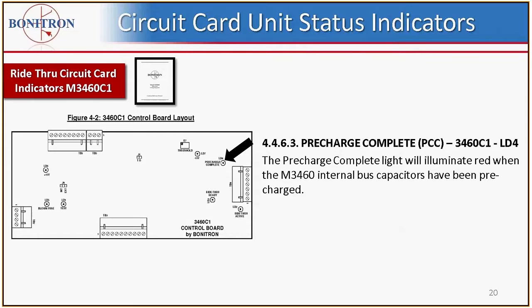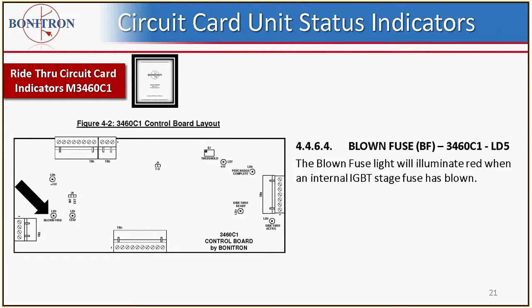Also on the control card is a pre-charge complete light. The pre-charge complete light illuminates red when the M3460 internal bus capacitors have been pre-charged. This has nothing to do with the drive. The blown fuse indicator on the C1 board illuminates red when an internal IGBT stage fuse has been blown. As I said, there are stages in the ride-through when you get over 50 kilowatts. So it's one stage per 50 kilowatts, and each stage has signals that feed this light, and that tells you an IGBT stage fuse has blown.